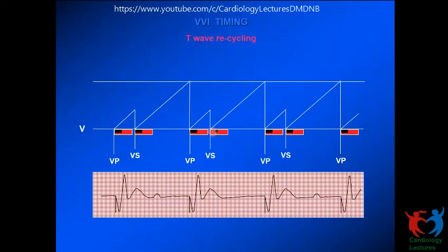And then here is a T-wave oversensing that is happening, and in this patient, the QT interval seems to be slightly longer, and it is happening outside the refractory period. So here it is sensed as a ventricular sense, and it is actually causing a resetting of the clock and ends up pacing in the ventricle at this point. So your effective pacing rate is lower than the lower rate, because the actual effective time is longer than what we intended, which is maybe 60. But if the QT interval happened to be 300 millisecond, and if this lower rate interval is 1000 millisecond, then effectively we are pacing at an interval of 1300 millisecond, which would be something like 45 beats per minute. Your patient could be symptomatic.